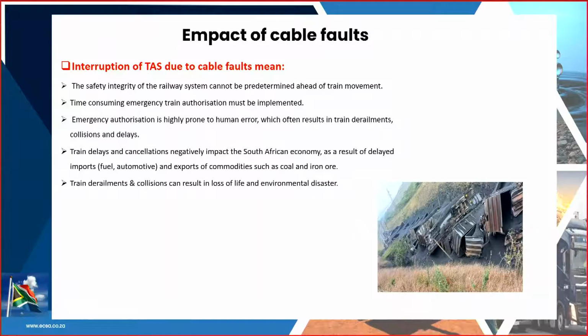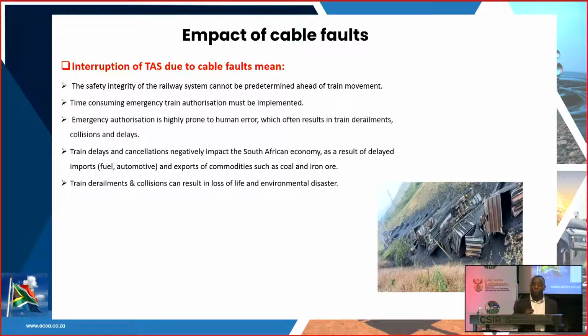We want to be able to detect this kind of fault so that we can plan our maintenance. Once an incipient fault occurs, once cable insulation damage occurs, if we can detect it, then we can plan how we are going to replace this cable before it leads to catastrophic failures that can cost us, as I will speak on the next slide. Now, at the moment, we are unable to detect the failure of the cable before it fails. So if the cable fails, it means that the train authorization systems that we so heavily rely on will not be able to function.